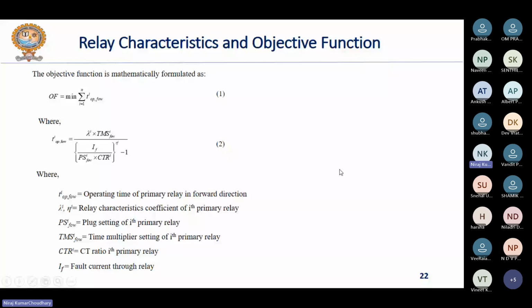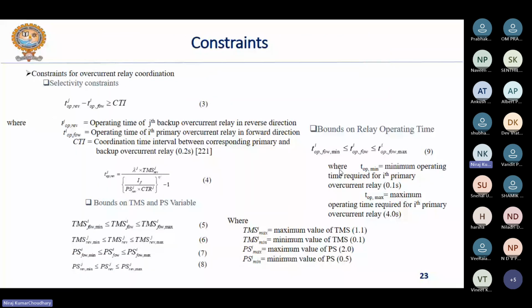So after the formulation of the objective function, you need to define the constraints. So this is the selectivity constraint, that is, the constraint related to the coordination time interval. As we have seen in the figure, the time of operation of the primary relay should always be less than the time of operation of the backup relay. So the difference should be greater than or equal to your coordination time interval. Now, depending upon the type of relay used in the system, whether you are using electromechanical relays or microprocessor based digital relays, the value of the CTI changes. Normally, it varies from 0.2 to 0.5 second, right? But you can adjust its value depending upon the type of relay used in the system.